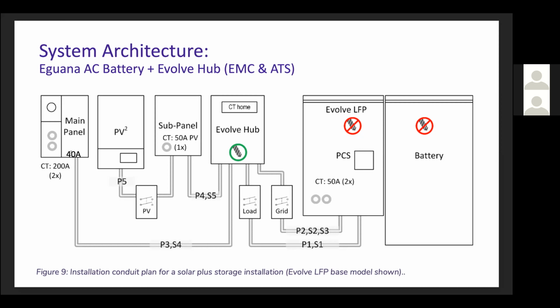And one of the nice features is that the Evolve Hub will pass through up to a 40 amp circuit, or that 7600 watt PV inverter, while grid tied. Those loads will be served in the sub panel while grid tied or in off grid mode. Any excess PV is passed through the hub to this common connection. So if that PV inverter was originally connected to that 40 amp breaker, you would disconnect the PV from that 40 amp breaker, connect it through the new backup load sub panel, and then through the Evolve Hub, and then reuse that same 40 amp interconnection.